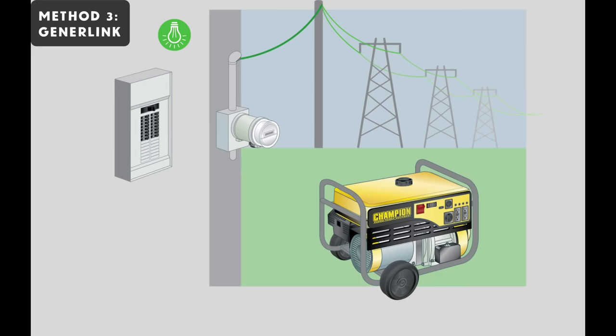Now, there's one other thing I need to mention about this option. Not all jurisdictions in the world have approved the GenerLink to be installed. They haven't all got around to studying it and accepting the existing approvals. So, before you go out and buy anything, you should contact your local electrical authority. Just see if they permit this kind of hardware, the GenerLink, to be installed. And if they do, then you're good to go. If they don't, then really your best option is some sort of a transfer switch and panel arrangement.